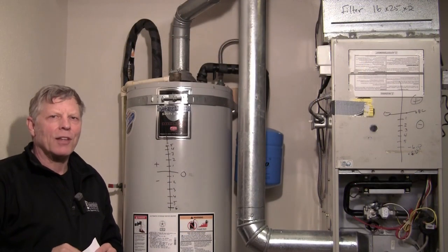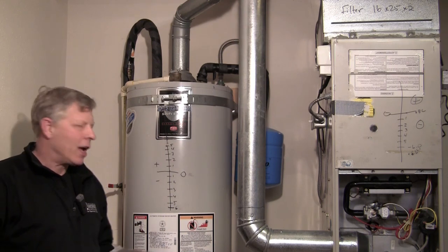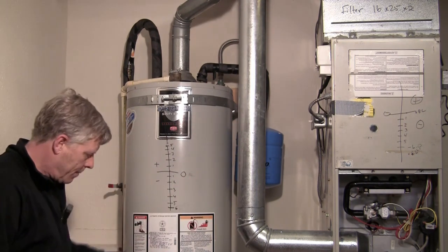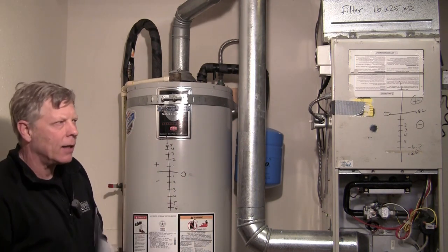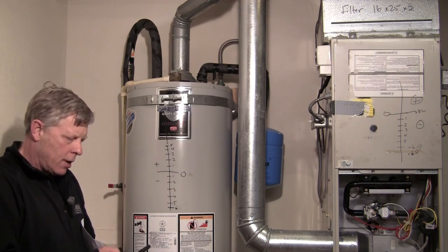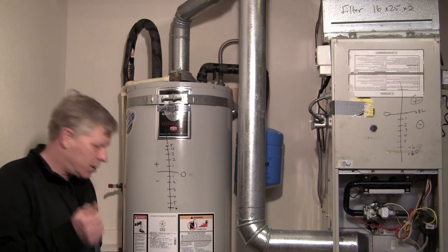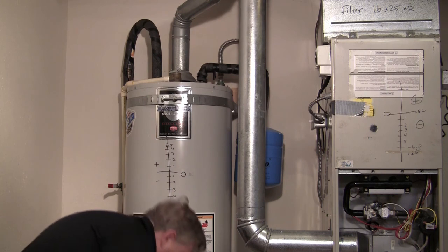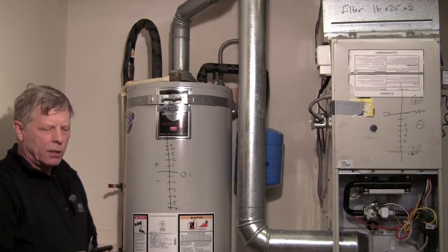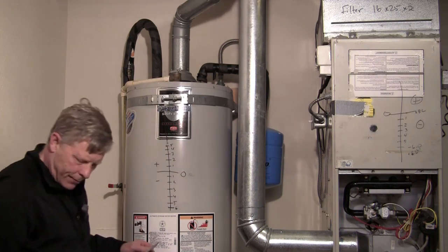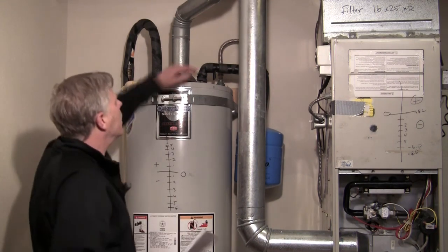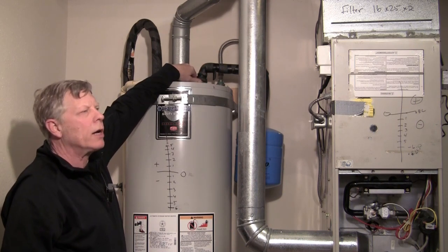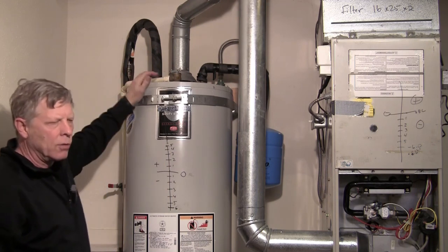Alright, I've got the combustion appliance zone back in worst case. We're getting ready to test the water heater. After we test that, we're going to move on to the furnace. So here we go. I've got to get my timer going for my spillage. I've got 2 minutes to establish draft, so I'm going to go ahead and turn on my water heater. Okay, I have ignition, so I've got 2 minutes to establish draft. Put my timer down here. I can feel and smell the spillage right now coming out of the water heater draft hood. I'll check it with smoke at 2 minutes.